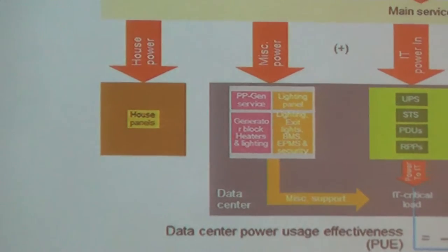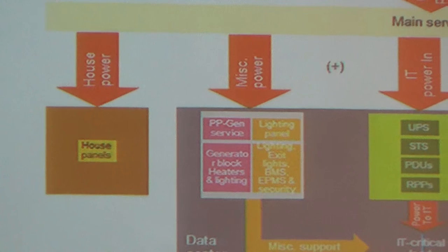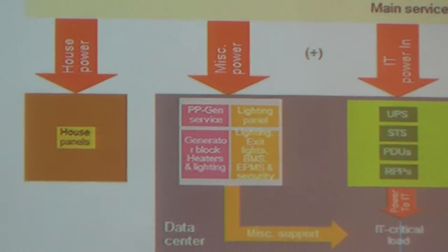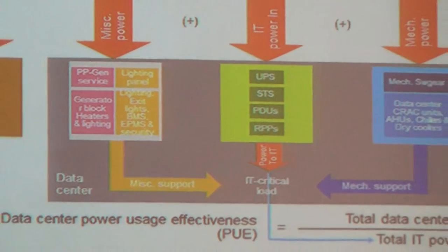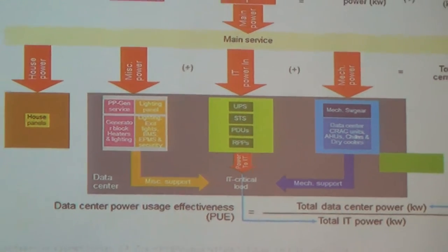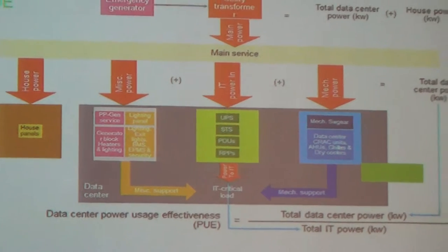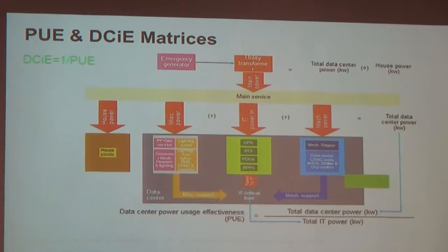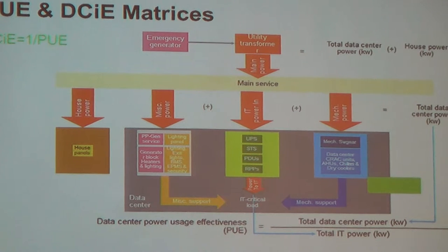It's very important, as the keynote speaker said, to look at how much energy we waste before we get to where it needs to be used. We have 100% energy at source. By the time we get it into our data center, it might only be 60% of the total. By the time we've powered our UPSs, diesel generators and PDUs, we might be down to 40%. And of that 40%, over 50%—I think at the moment it's 52%—is not used on IT equipment, it's used on mechanical and electrical equipment.